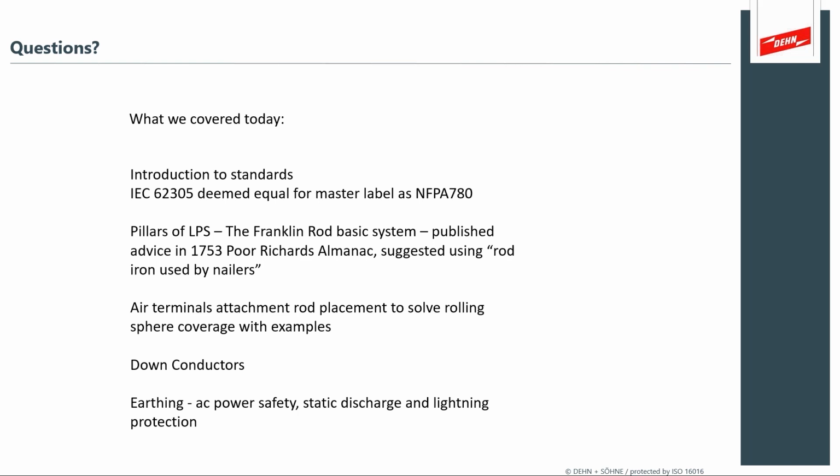Yeah, if you're within that distance, the intent is to bond it. So that down conductor would come down the side of a building, and if the building has metal flashing, you want to bond it at the top and bottom. You see a lot of these prefabricated buildings with this. There's a brand name called Nucor, and it's a thin aluminum sheet with a foam core, and it's way too thin to serve as a natural down conductor. But if you don't bond it, it'll spark to it anyway.